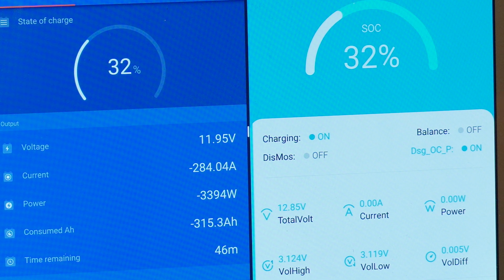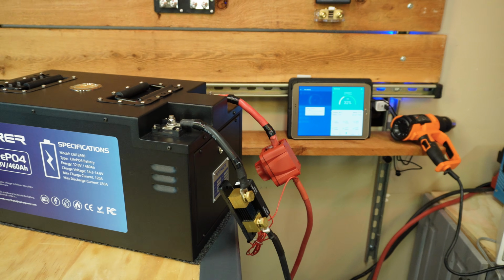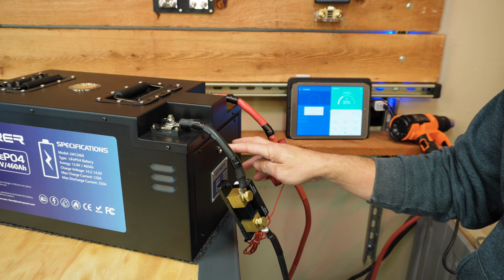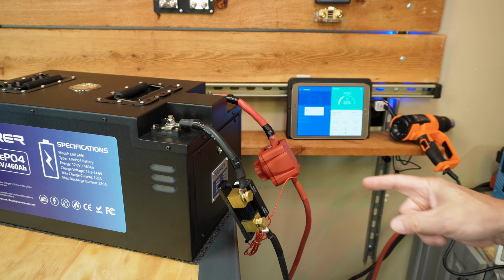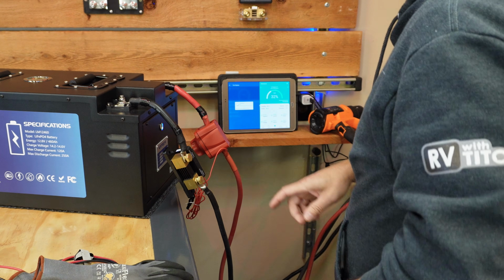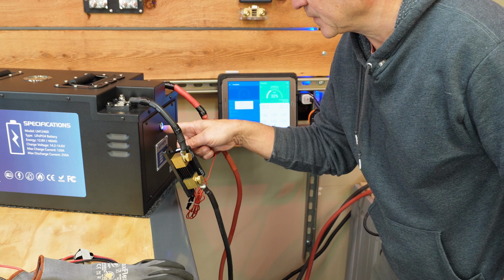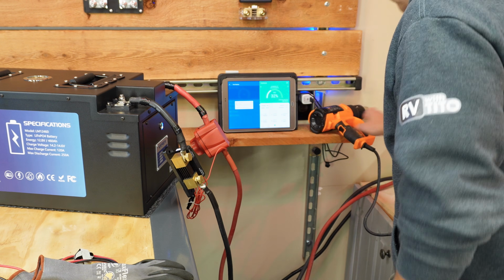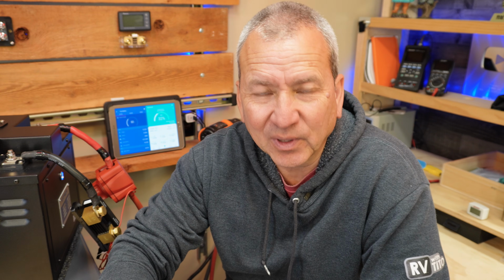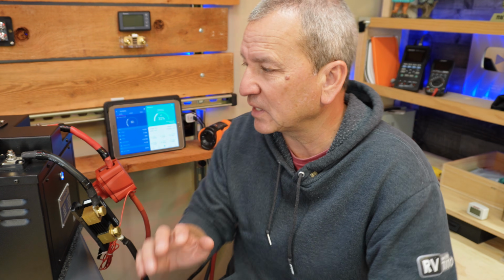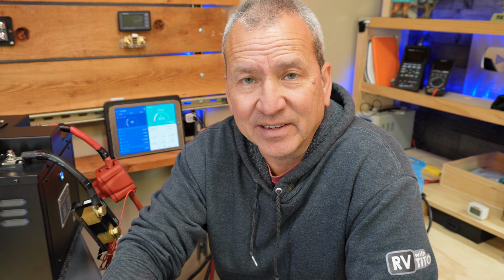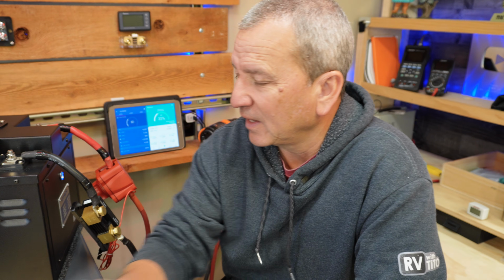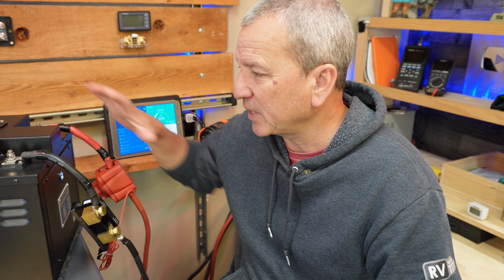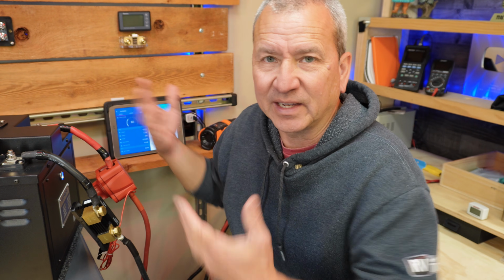Oh, there it goes, the battery shut down. I can see the power light is out, but we'll see what happens. Oh, it just came back on again. Well, it was able to pull over 250 amps for a few seconds. It took about 10-15 seconds for it to actually disconnect, and it was at about 275 amps when it did. After about 30 seconds or so, the BMS reset itself, and then it came back alive again.